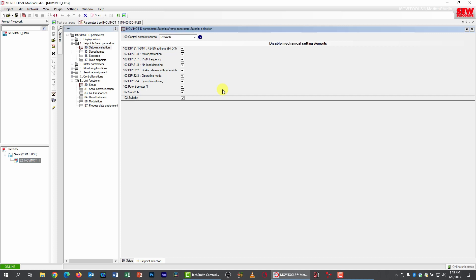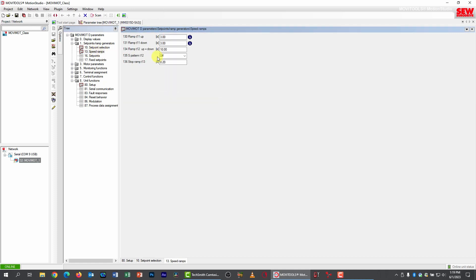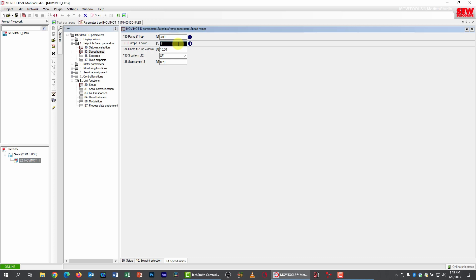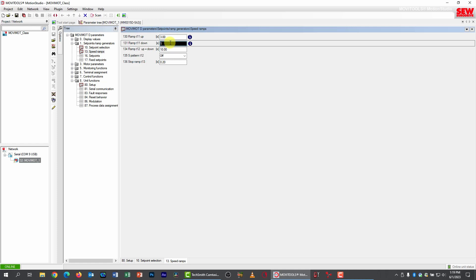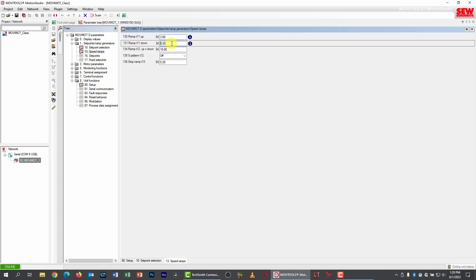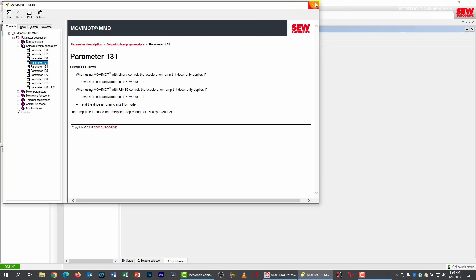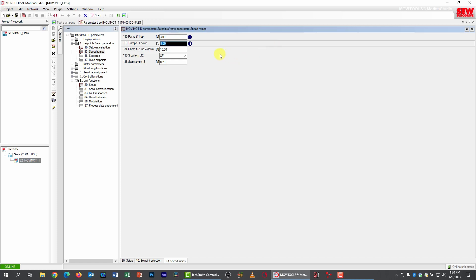I'm going to disable all checkboxes so I have full parameter control. Now let's take advantage of the independent ramps. I go to subgroup 3 under parameter group 1, speed ramps. The up and down ramps give independent control for normal speeding up and slowing down — right now they're set to 3 seconds by default. I'll change the down ramp to 5 seconds. Remember, always hit Enter after changing a parameter. If you just click to another parameter, notice it reverts back to 3 — the only way to change a parameter is to type it in and then hit Enter.